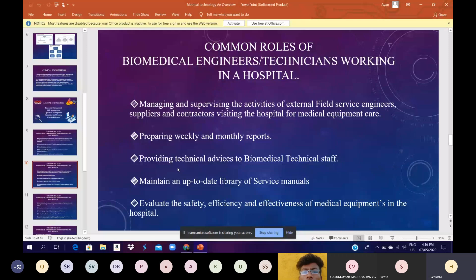of the medical devices available. Evaluate the safety, efficiency and effectiveness of medical devices in the hospital. This is another important factor. You have to do periodic inspections in all the clinical areas in order to identify the problems, if any. Sometimes the end user may not notice if the machine is not in use for several days. So if you do the periodic inspection in different wards or locations in the hospital, you will be able to understand if there is a problem. You go and do the physical inspection, and also if you switch on the machine and check the functionality, if there is a problem, you can clearly understand and you do the corrective maintenance or proactive maintenance. So this is one of the major roles of biomedical engineers.